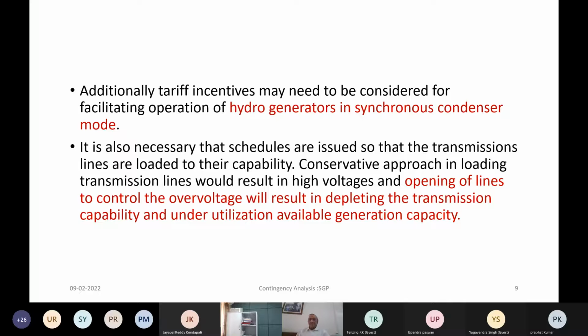And as I mentioned, this is again a statement from the CEA report that it is also necessary that schedules are issued so that transmission lines are loaded to their capability. A conservative approach in loading the transmission lines would result in high voltages, and opening of the lines to control the overvoltages will deplete the transmission capability, and it will be underutilization of the available generation capacity.